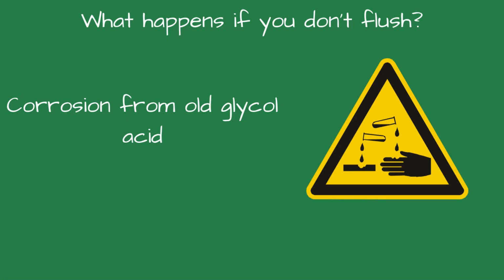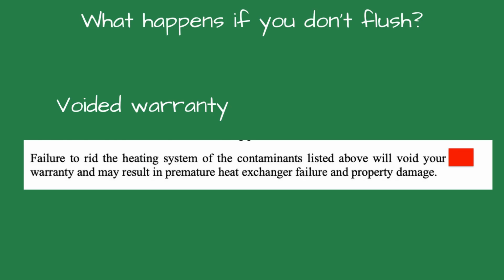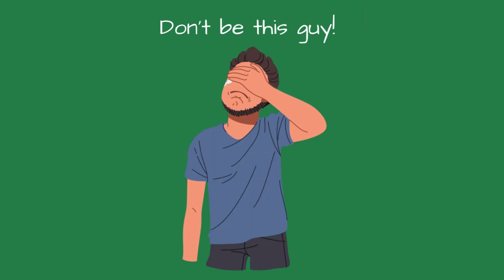And I think the most important is voided warranties. If a manufacturer finds evidence of dirty water or glycol in a failed boiler or pump, warranty coverage is unlikely. Many manuals state explicitly that water quality and system flushing are installer responsibilities. Imagine replacing a boiler in a facility where glycol has been circulating for 2 decades without maintenance. Instead of protecting the system, the glycol has broken down and is now acidic. The new boiler is connected without flushing, but within months, the owner notices reddish water and leaking pump seals. By the end of the first heating season, the high-efficiency heat exchanger is already showing signs of pitting corrosion.